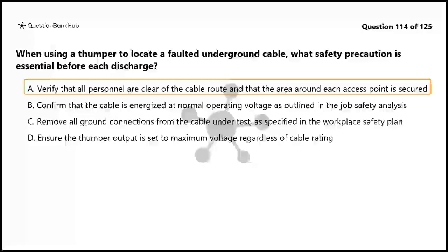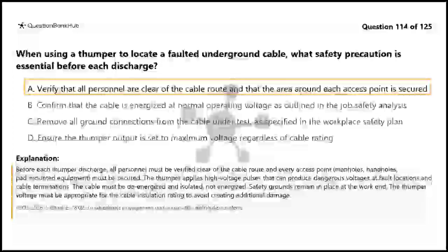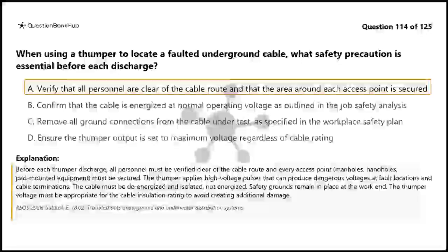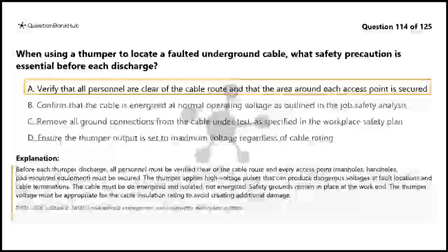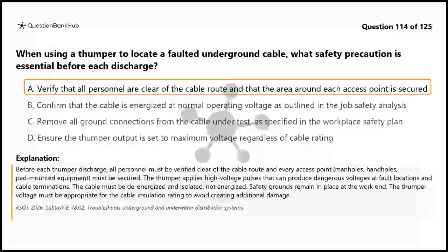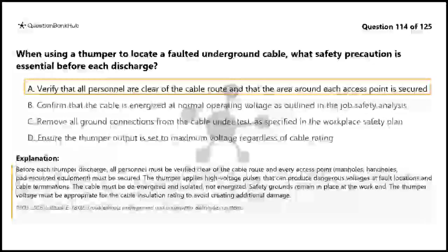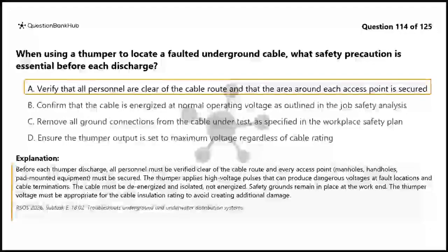The correct answer is A. Before each thumper discharge, all personnel must be verified clear of the cable route and every access point, manholes, handholes, pad-mounted equipment, must be secured. The thumper applies high-voltage pulses that can produce dangerous voltages at fault locations and cable terminations. The cable must be de-energized and isolated, not energized. Safety grounds remain in place at the work end. The thumper voltage must be appropriate for the cable insulation rating to avoid creating additional damage.